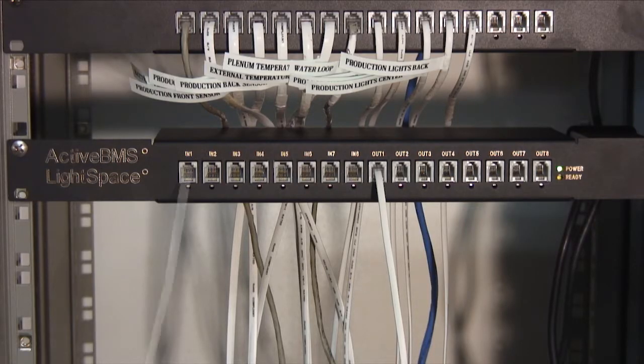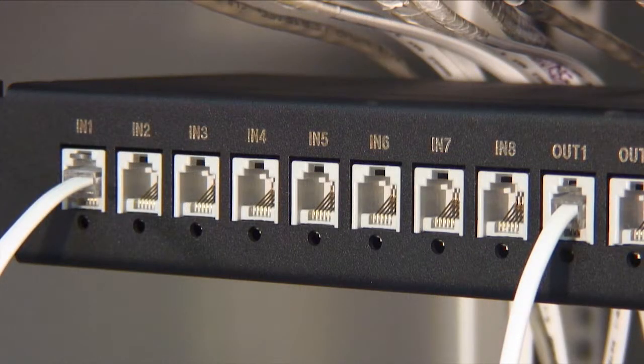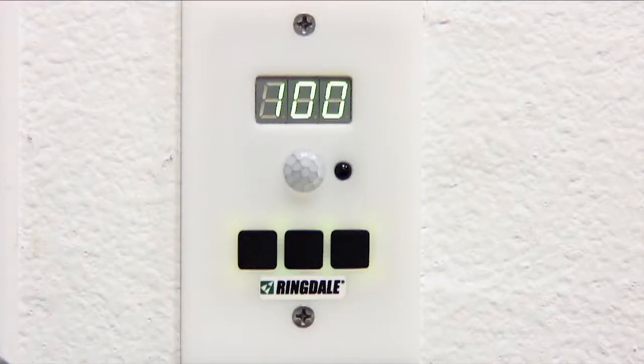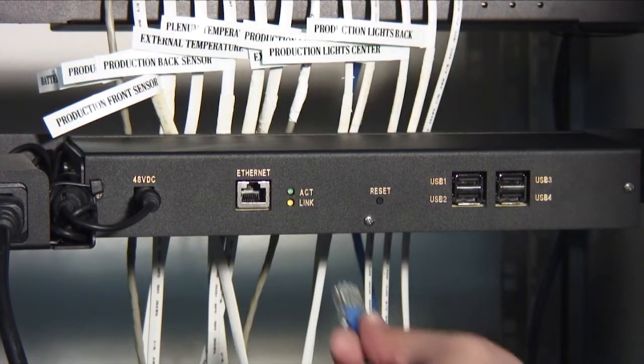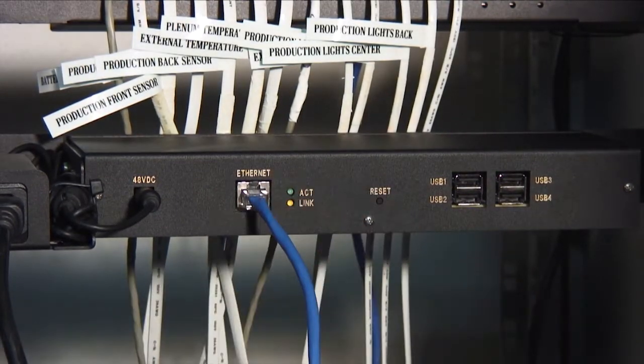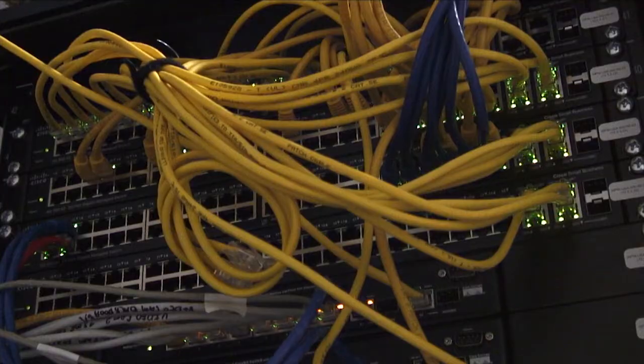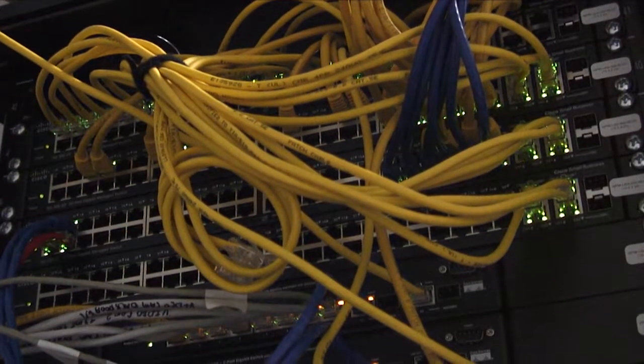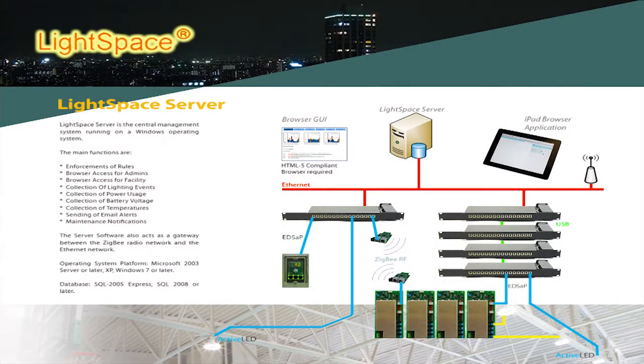An input port can be associated with the lighting zone's output port and a Lightspace manager connected to that input. An Ethernet network cable coming from a switch can be connected to the LSC. An LSC can communicate with other LSC devices via broadcast and to a server. Event data is collected directly from EDSAP sensors and light fixtures by the LSC and transmitted to the server for collection. The server also has control over input and output devices, allowing the reprogramming of wall or ceiling mounted LSM devices from a central location.